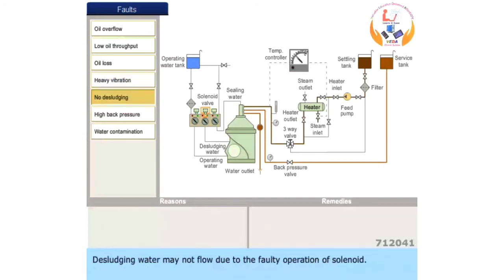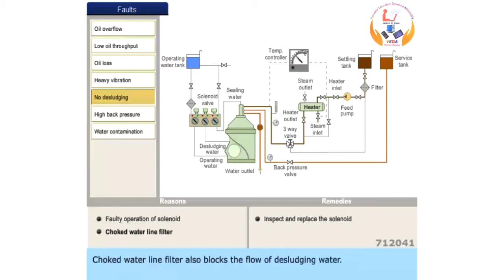Desludging water may not flow due to the faulty operation of solenoid. Inspect and replace the solenoid. Choked water line filter also blocks the flow of desludging water. Clean the filter.